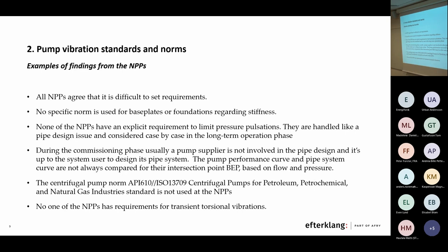Otherwise, as you know, you can limit the pressure pulsations with a correct piping system, with different damping methods or pipe resonances which are not tuned to the pressure pulsation frequencies. But it's also complicated because, as you know, there are a lot of harmonics in the pressure pulsations.